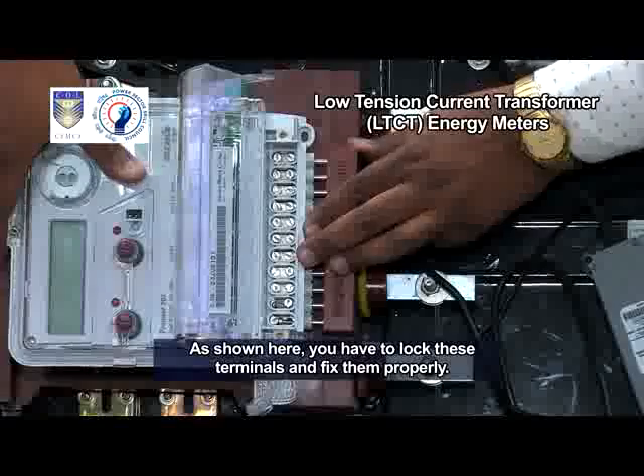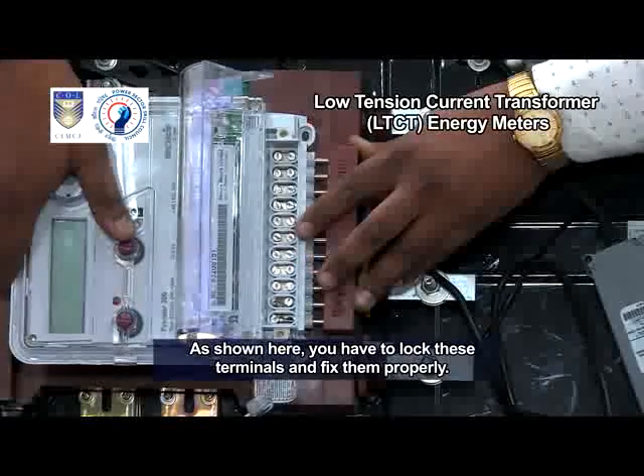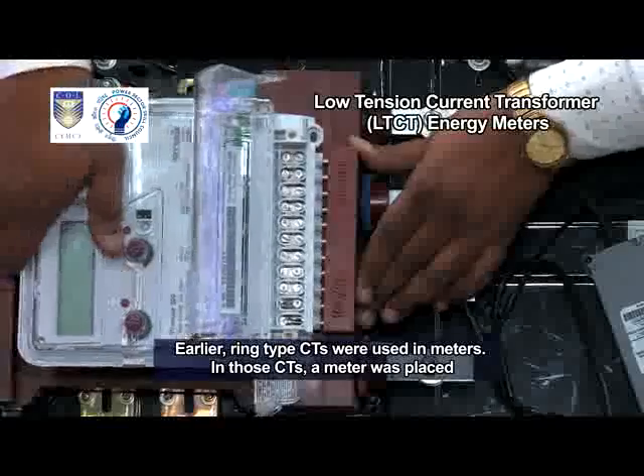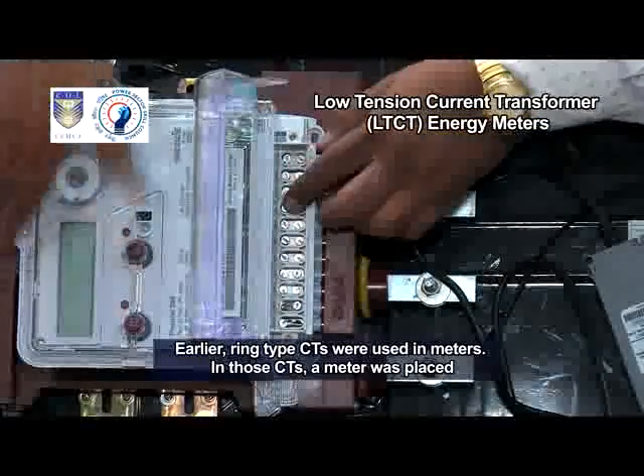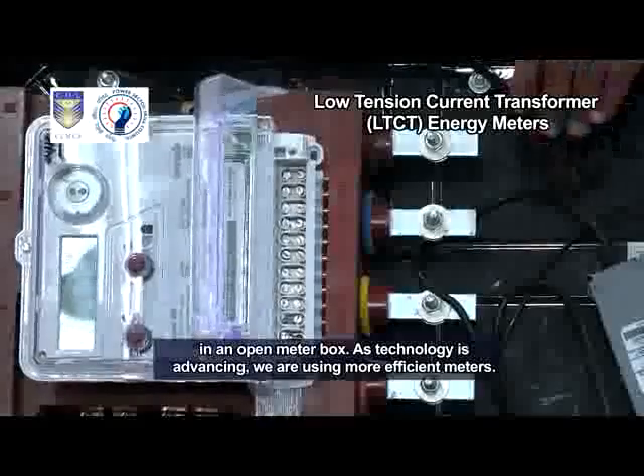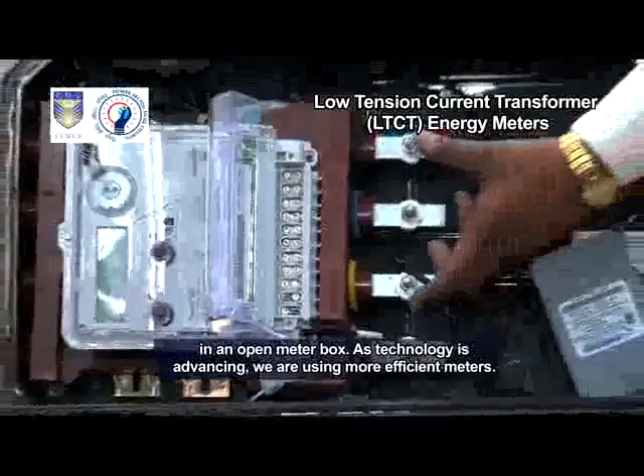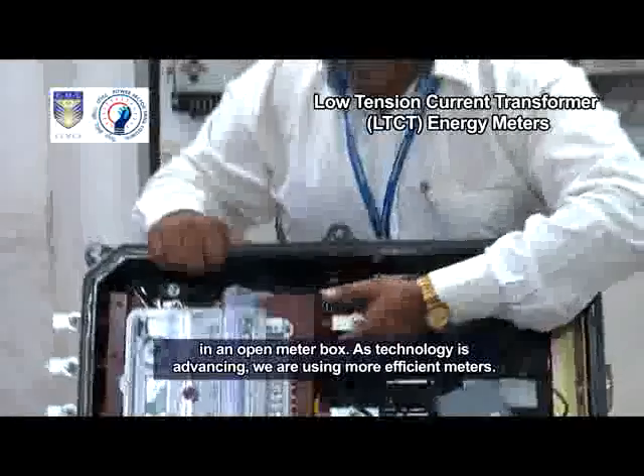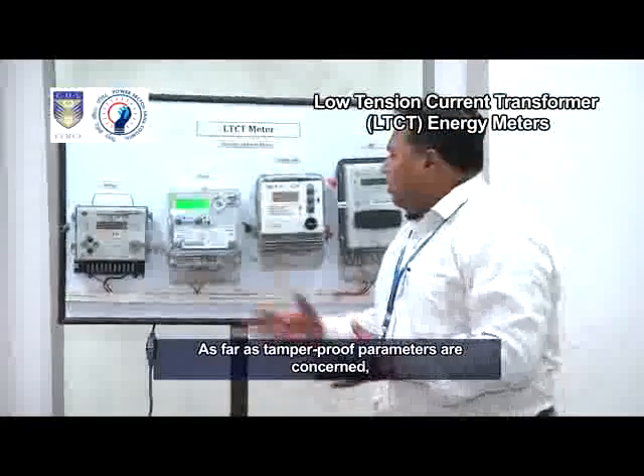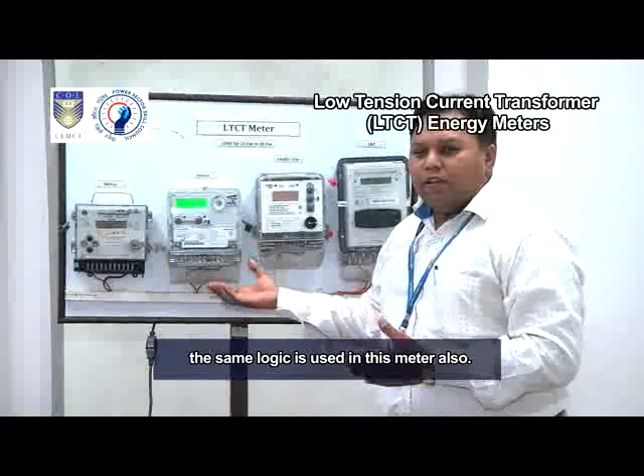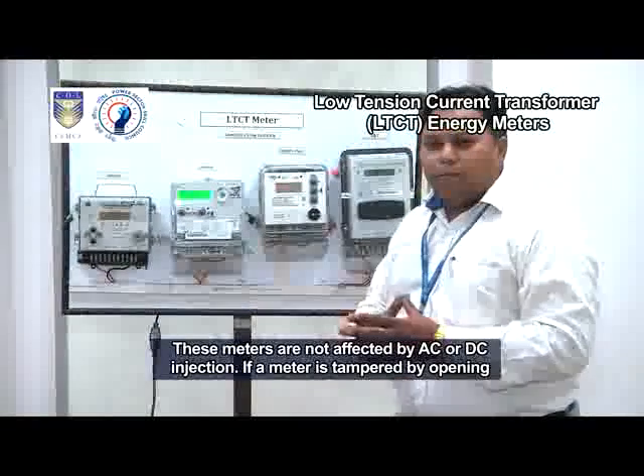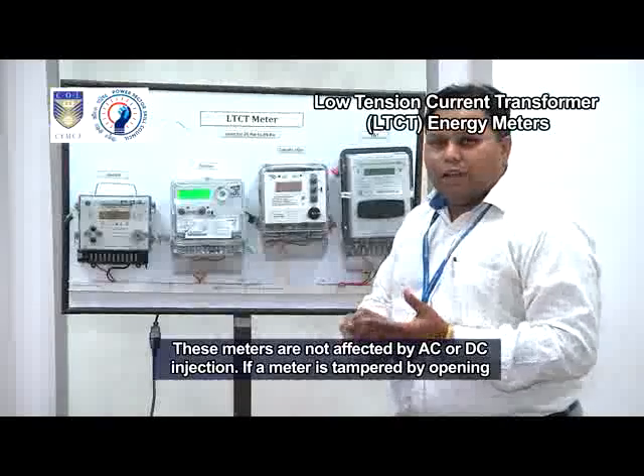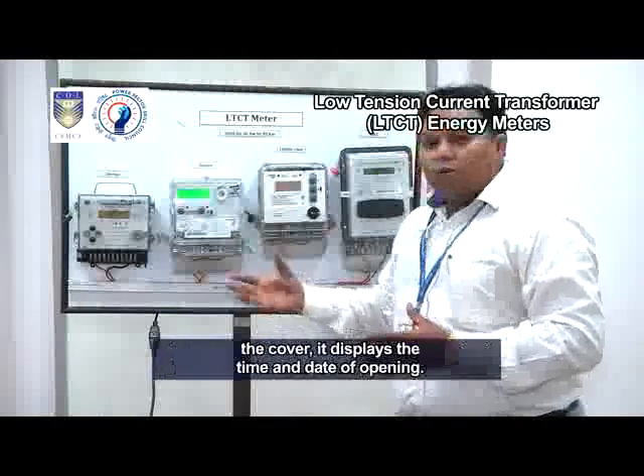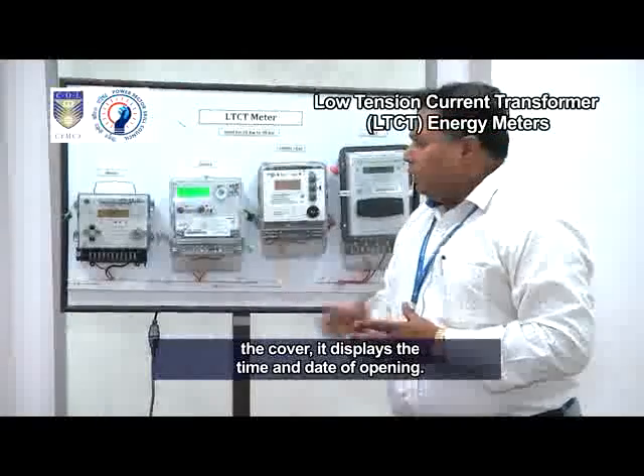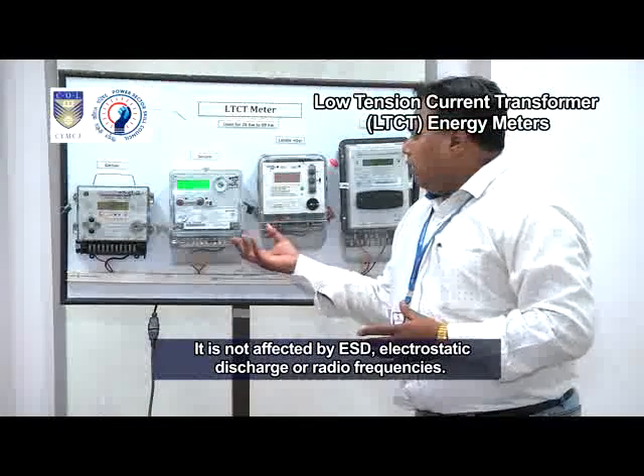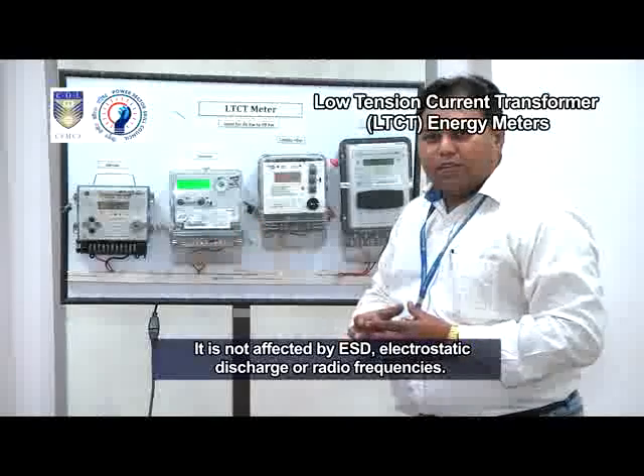As shown here, you have to lock these terminals and fix them properly. Earlier, ring-type CTs were used in meters. In those CTs, a meter was placed in an open meter box. As technology is advancing, we are using more efficient meters. As far as tamper-proof parameters are concerned, the same logic is used in this meter also. These meters are not affected by AC or DC injection. If a meter is tampered by opening the cover, it displays the time and date of opening. It is not affected by ESD, electrostatic discharge or radio frequencies.